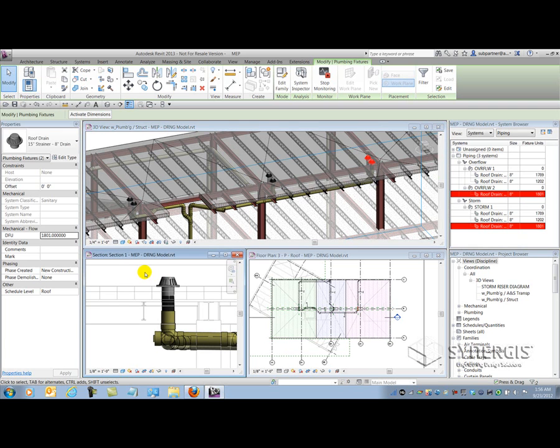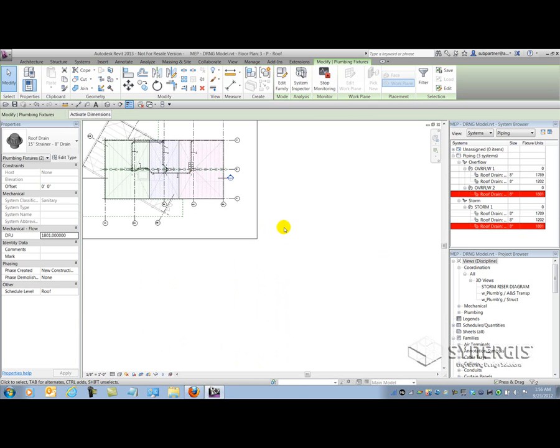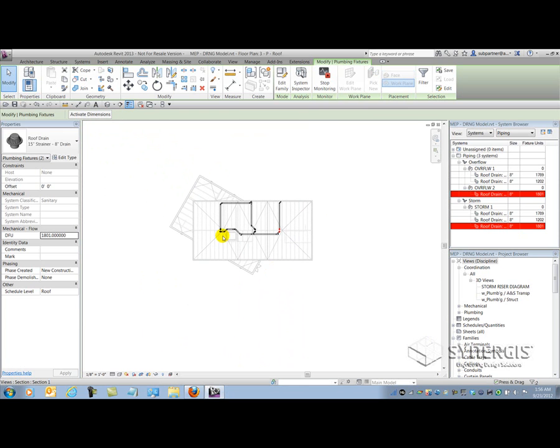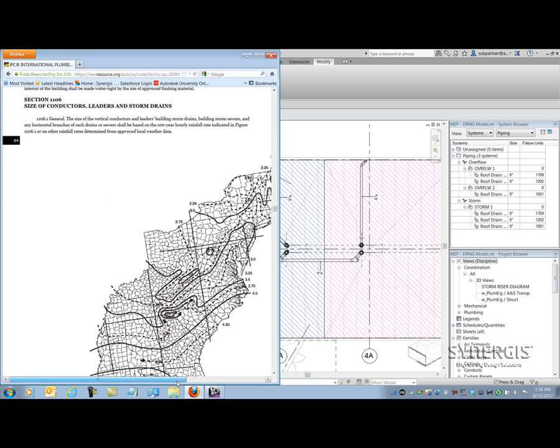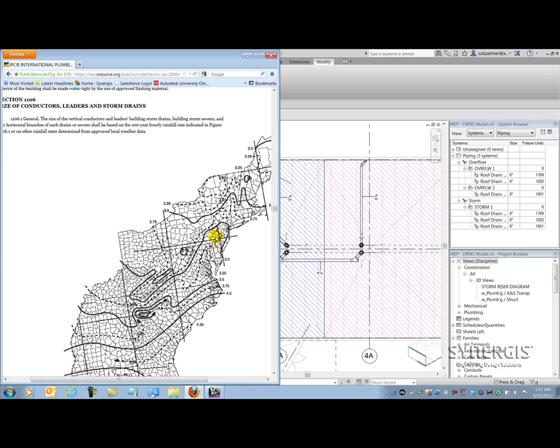Now that that's understood, I can start to analyze the system. I'm going to utilize the code — I'll base this off the International Plumbing Code. One thing it states is that your building has to be located geographically, and based on that geographic location you're going to get an average rainfall every 100 years, and you have to size your system for that. So pulling up the International Plumbing Code and looking at our building's location — we're going to be located in Philadelphia — we fall roughly around 3.1 inches of rainfall for the 100-year storm. That's going to help us size our leaders and conductors based on Section 1106 of the IPC.